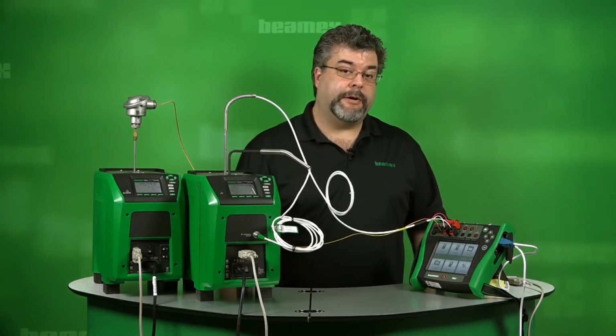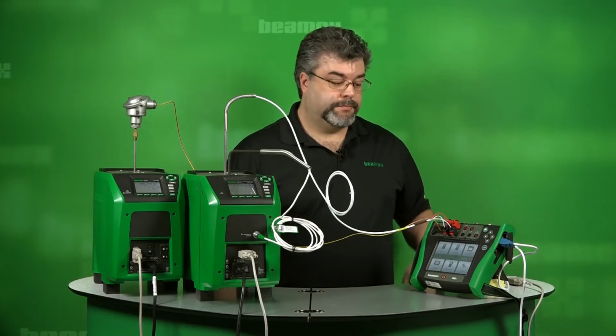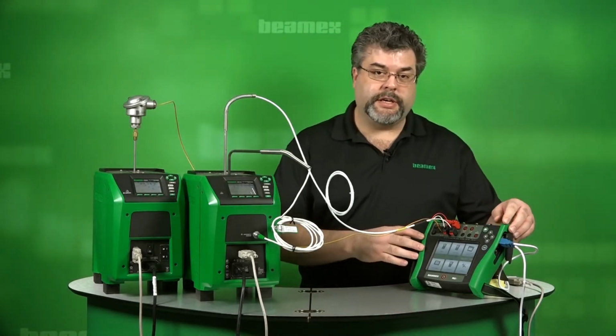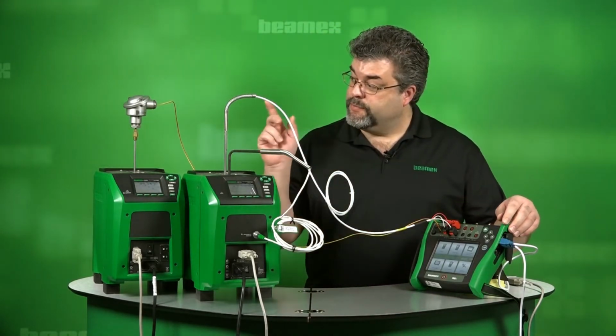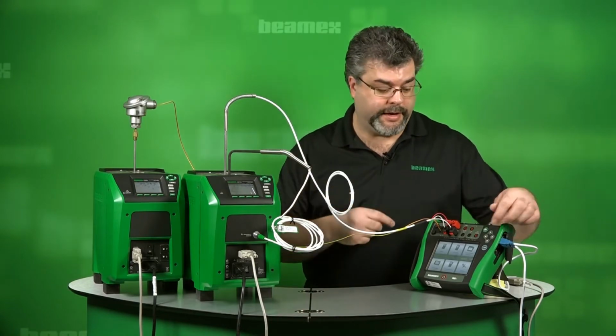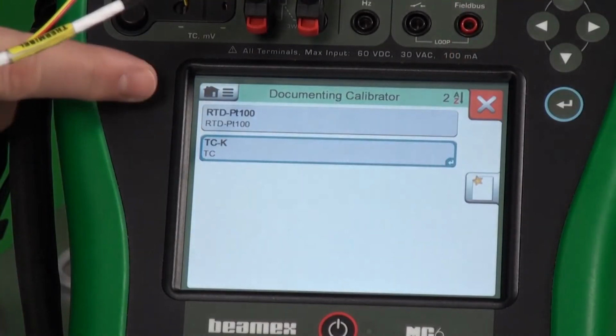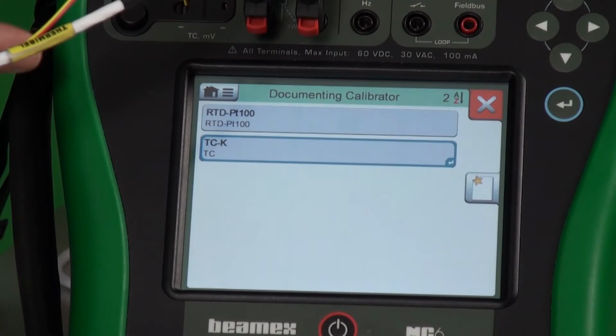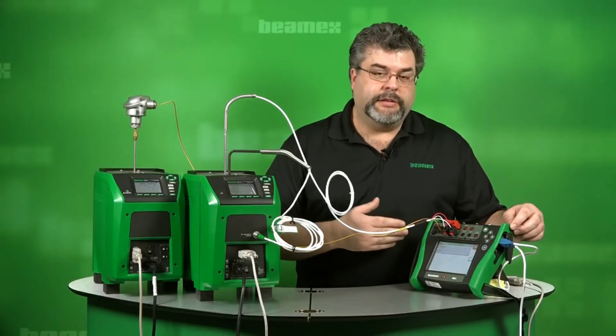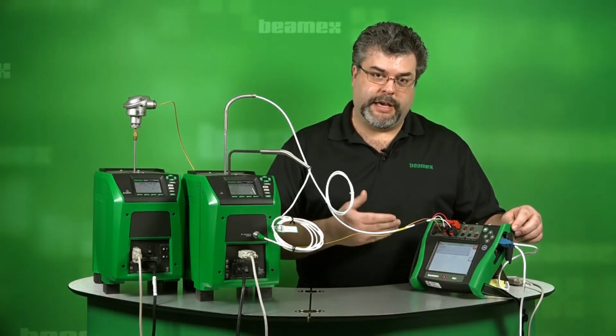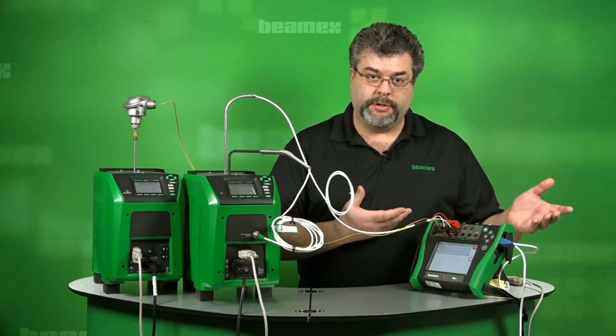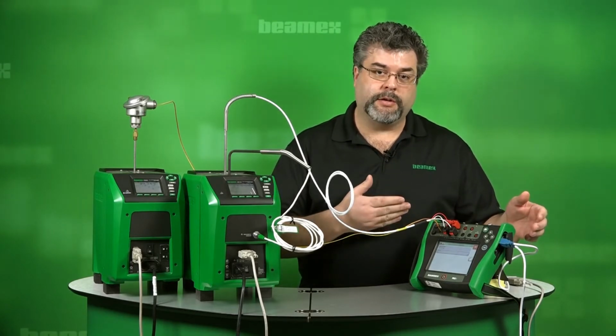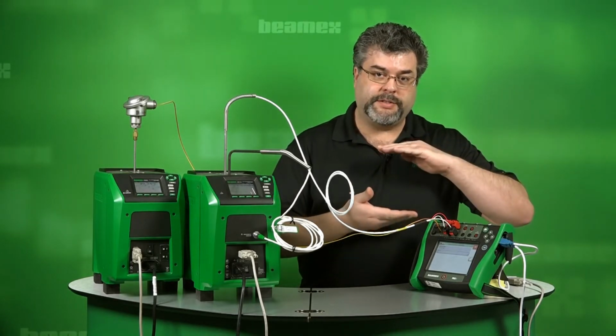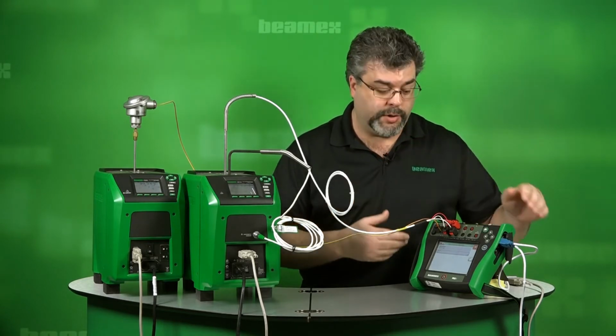Let's take a look at our documenting calibrator. On the MC6, we have 2 tests predefined. So let me go to documenting calibrator. Here they are. We've got an RTD, we have a thermocouple. We allow you to group tests together, and we use the term group to do that. So when we hit start, we'll combine both of these tests and run through them all sequentially.